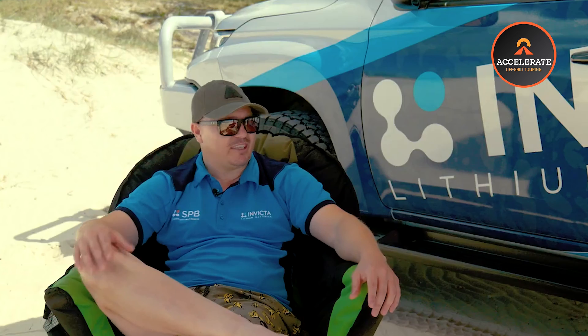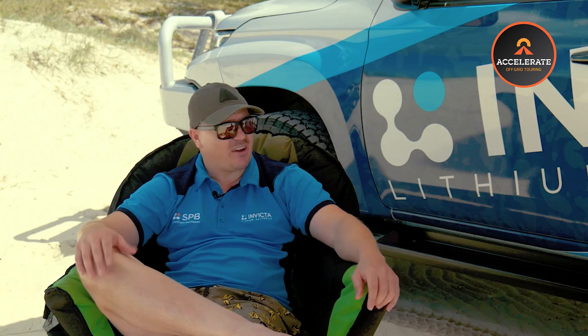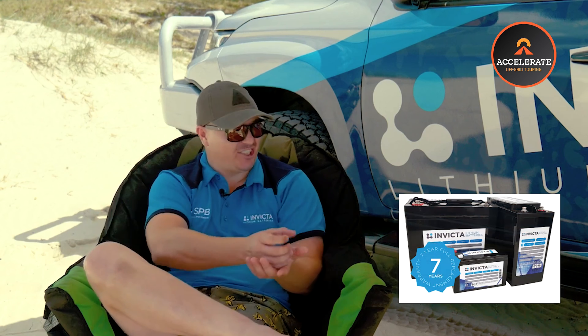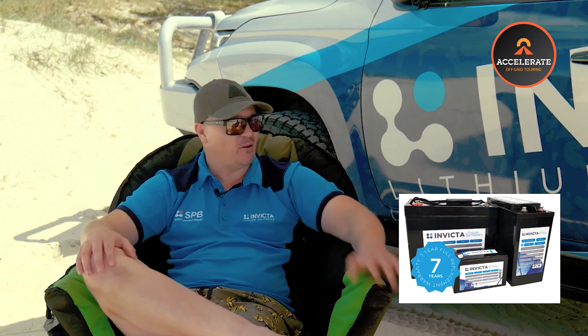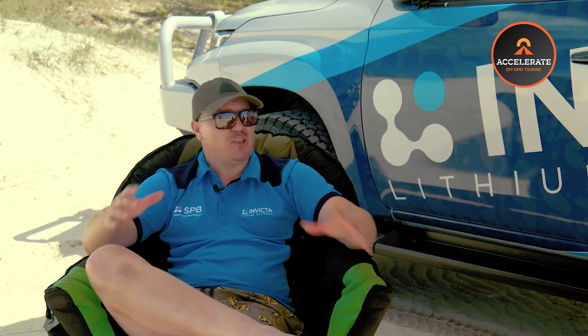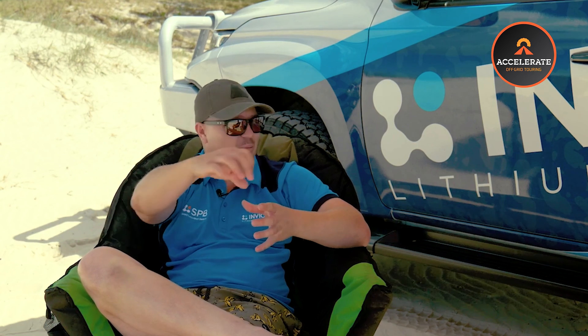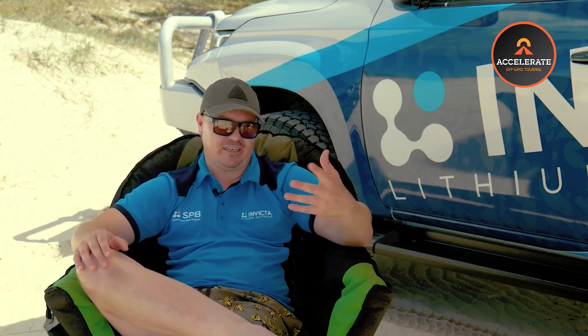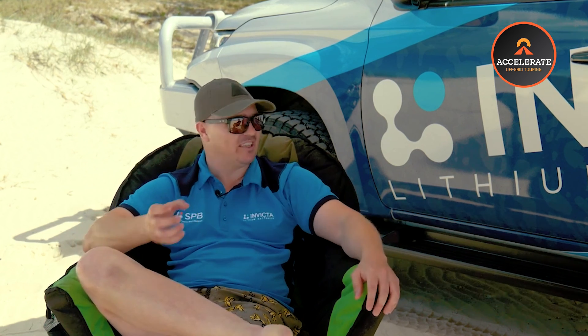One key thing to keep in mind when researching IEC certification: make sure that certification is on the whole battery, not just at a single cell level. Invicta does hold IEC 62133 certification at the single cell level, but you want the full battery certified because that tests the single cell in conjunction with the other cells, the bus bars, the BMS, all the wiring — the entire unit — for safety and quality, which is far more important than how a single cell reacts in a failure scenario.